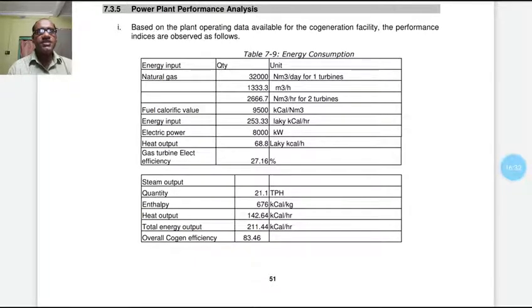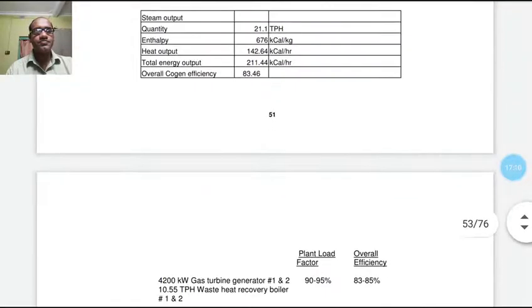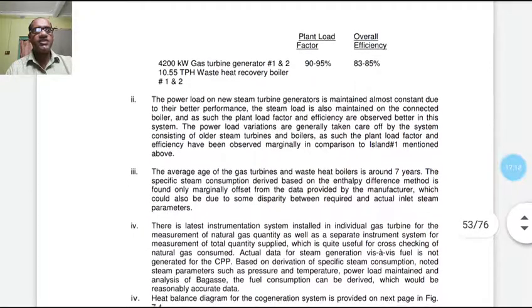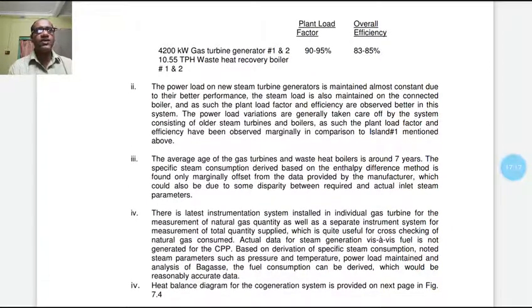Gas turbine electric efficiency is 27.16%. Next, steam output quantity 21.1 TPH. Enthalpy 676 kilocalorie per kg. Heat output 142.64 kilocalorie per hour. Total energy output 211.44 kilocalorie per hour. Overall cogeneration efficiency is as high as 83.46%, that is the combination of gas turbine and waste heat recovery plant. Now, plant load factor is varying from 90 to 95 for gas turbine generators 1 and 2 and the waste heat recovery boilers of 2. Overall efficiency is 83 to 85%.